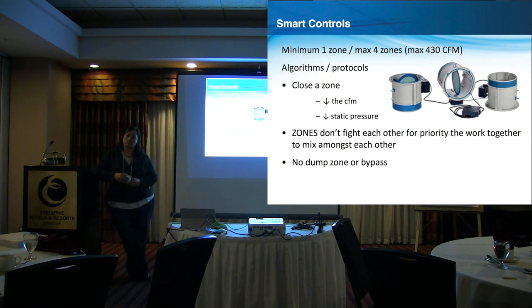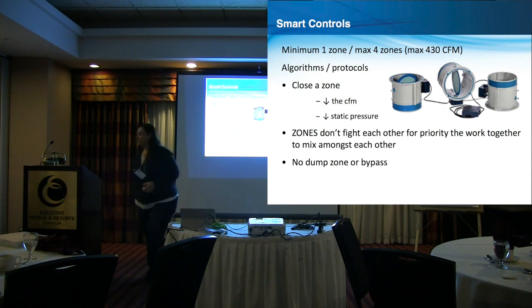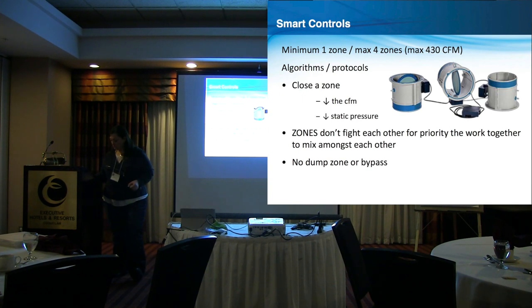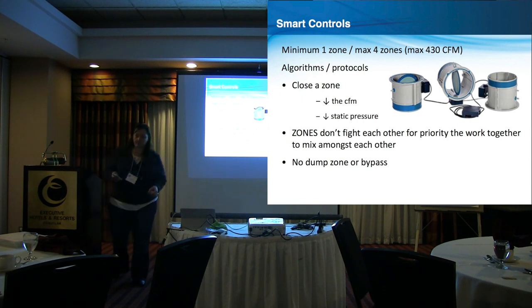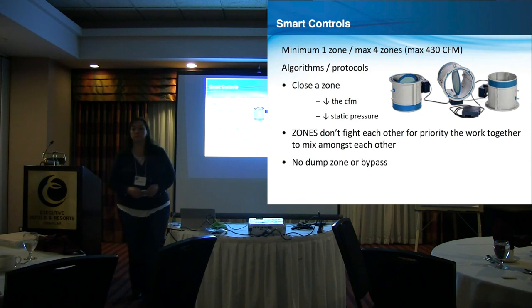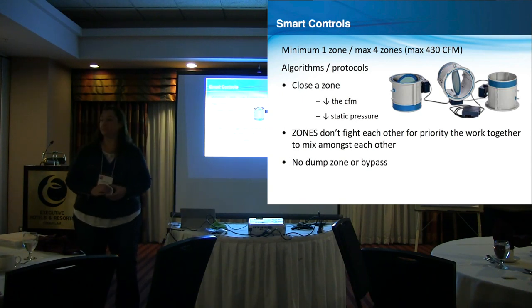The motor will go up to 1.7 inches, so it'll ramp up. You can do 200 feet of duct, or you can do 20 feet. If you're doing 200 feet with 10 items on it, you're going to have higher static. It doesn't give you a fixed static, it gives you a fixed CFM. It's a constant CFM motor. That's what I meant with the platform, if you guys are not familiar. It's just like a GE communicating, the Emerson Climate Talk. So it's constant CFM and it will change based on the static. Oh, okay.